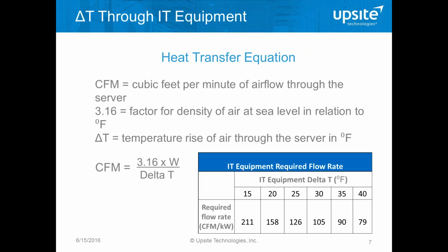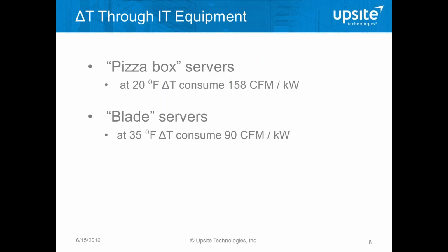Next. And we look at those differences based on the fixed relationship between airflow and delta T. And delta T here we're talking about the amount of temperature rise of the cooling air as it moves through servers. That's a fixed relationship, and we see here in the chart where we have a low delta T, we have a pretty high airflow demand, and we have higher delta T, so we have a low airflow demand. And that difference ranging from 211 CFM per kilowatt down to 79 CFM per kilowatt is a pretty extreme variation. And if we look at the example on the next slide, it'll show how that actually plays out.